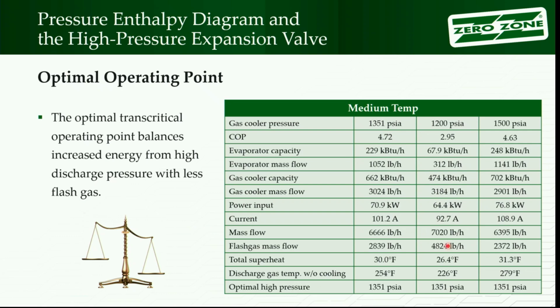Discharge temperature, notice what's happening there. A lot of what we expect, right? The higher the discharge pressure, the higher the discharge temperature. This system, the software may be starting to say you're done at 1500 psi because I'm getting up to 279, right? That second override's going to come in and kick that back.